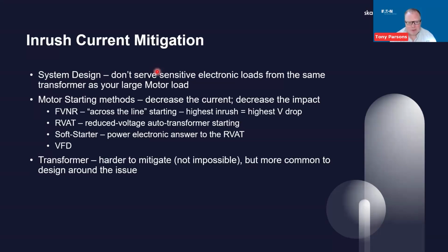Just trying to get some segregation in that sense can go a long way. We talked about motor starting inrush, and there are motor starting methods that can be used to help decrease the inrush currents. If you decrease the current, Ohm's law says we have less voltage drop, so we're going to decrease the impact as well. The baseline, what we would call in the US FVNR, or just across the line, full voltage starting, is the highest inrush. But maybe you could put on something like an auto transformer starter, supplying a reduced voltage to the motor to get it up and running, and then switch to the full line voltage, or a soft starter, kind of a power electronic answer to that auto transformer starter. The ultimate would be the variable frequency drive or the adjustable speed drive, which really starts the motor, I don't know if gently is the right term, but you bring up the voltage and the frequency together, really eliminating the inrush.